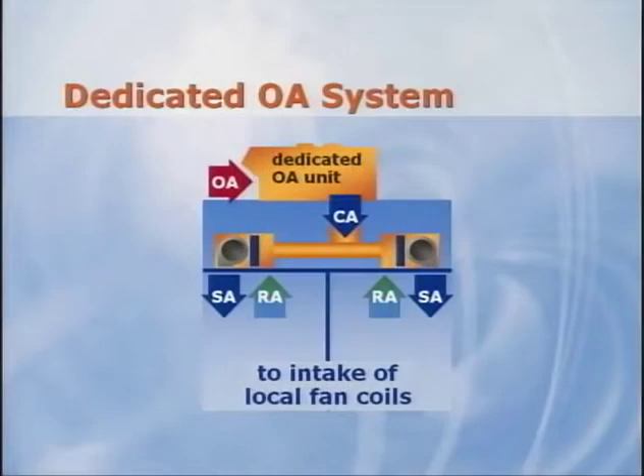Since this is the first of our systems to use a dedicated outdoor air system, let's get a better understanding of the strategies related to that. A dedicated outdoor air system devotes one air handler to condition all the incoming outdoor air used for ventilation. Meanwhile, the local fan coil unit handles the sensible load in each zone. The conditioned outdoor air is typically delivered to the zone in one of two ways. The first approach is to duct the outdoor air directly to the intake of each fan coil, where it mixes with return air from the zone. Then the fan coil maintains space temperature by cooling or heating this mixture.